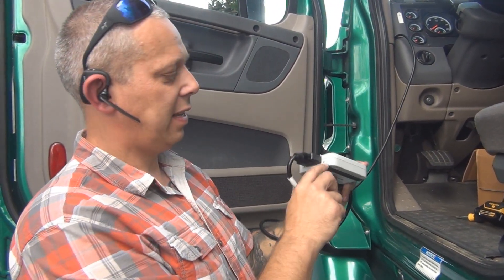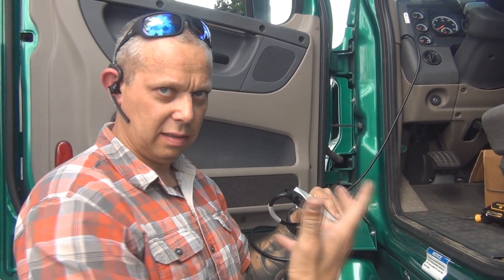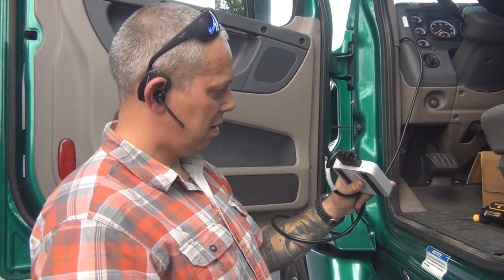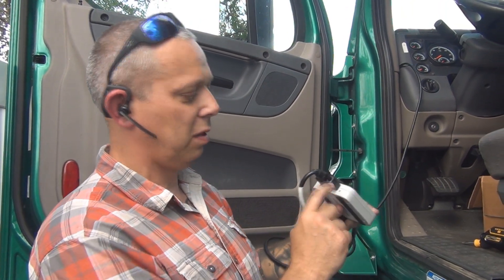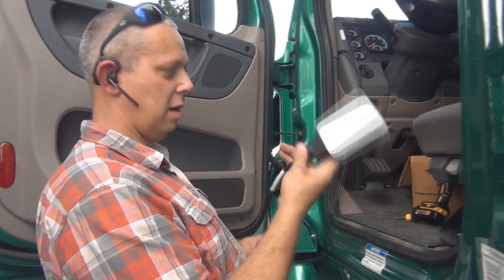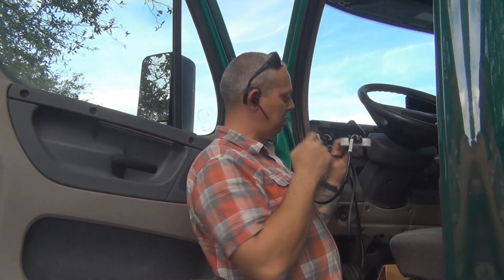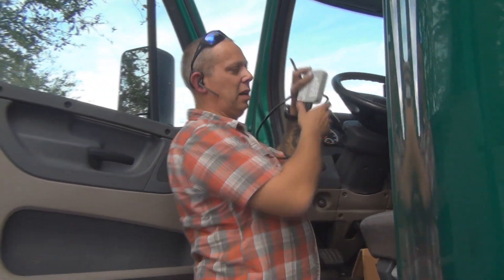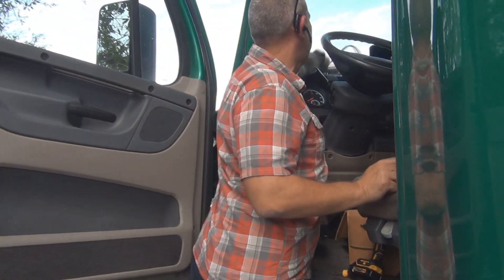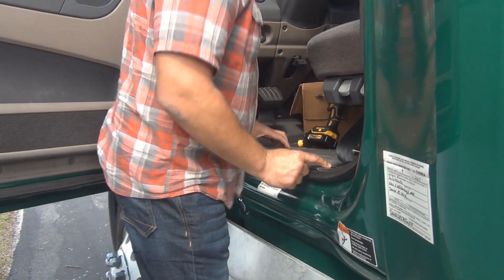On the right side, that light will be red because no Bluetooth-capable device such as a tablet or phone is currently connected. Once the driver comes over, he will connect by logging into the KeepTruckin app and making his Bluetooth connection — that red light will turn green. You always want to have the unit on the dashboard so the driver can see both lights. Wait until both lights are green before moving forward: one confirms connection to your device, the other confirms connection to the engine.